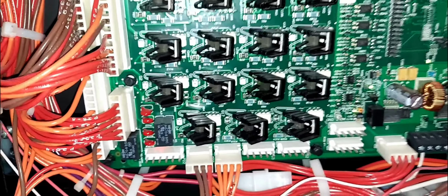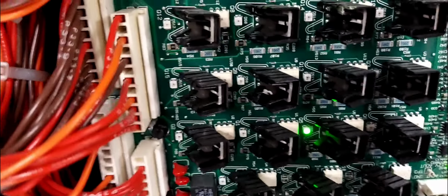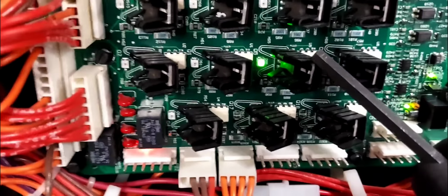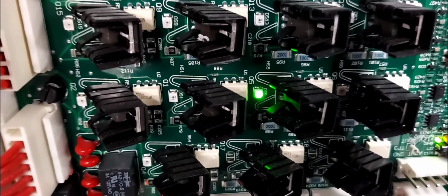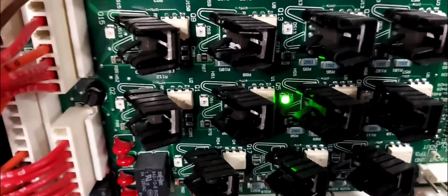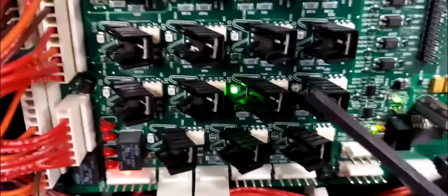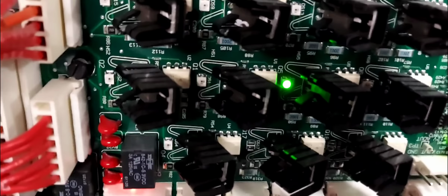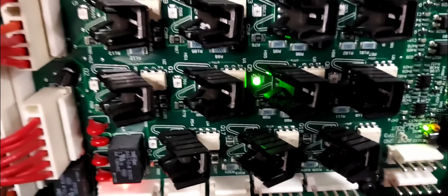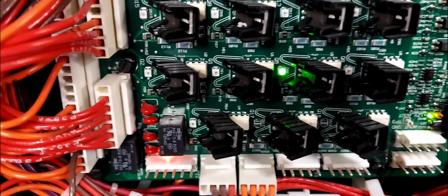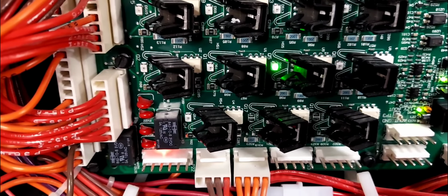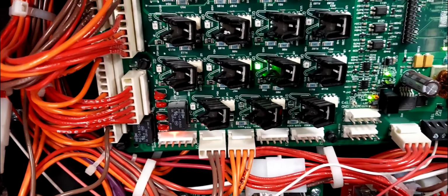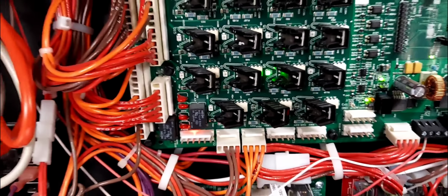And let me turn the lights off. Okay, so right now we got this right here. And you can see that the green LED is on. This right here is Q5. As you can see, it says Q5 on the board. Alright, so the triac is on, it's closed, it's passing 24 volts to the main fan contactor. Alright, so let's just see where we get that alarm. So get the lights back on.